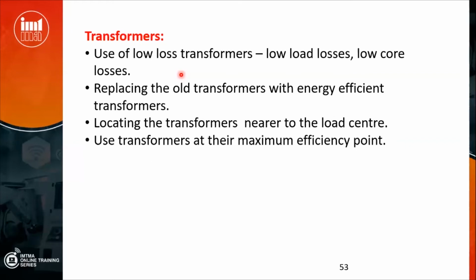Sometimes there will be loads as low as 20-25% in the night when all go asleep and there is no activity. And sometimes there will be 70-80%, 90%. So transformers are designed in such a way that the efficiency will be highest somewhere around 40-60% load, 70% load. If you operate at that load, it will be highly efficient.